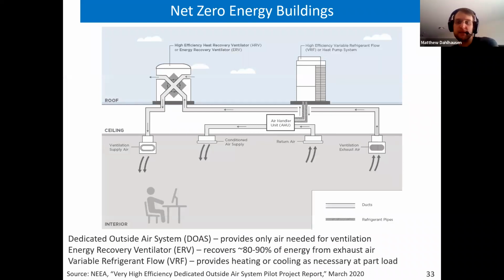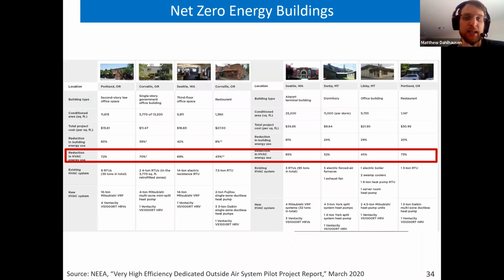Many buildings can be retrofit to be net zero energy. There was a recent pilot program that replaced HVAC systems on small commercial buildings in the northwestern US. They used dedicated outdoor air systems with energy recovery, providing only the amount of air needed for ventilation and meeting heating or cooling loads with a variable refrigerant flow system. Buildings in the pilot saved 45 to 85% of their HVAC energy use. The savings comes from moving a much lower volume of air and recovering most of the energy from the exhaust air.